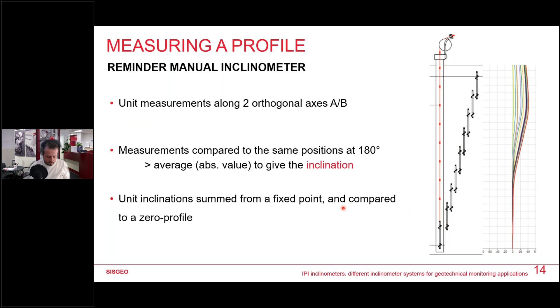So the unit inclinations are summed from a fixed point. You consider that your bottom point, for example, is 0, doesn't move. So it has to be real. If you choose this point as a reference, the reality should be exactly this. This zone will not move. And then you sum your local inclinations step by step in order to get a profile. Then you perform the measurement a second time. So you go on the field, you make exactly the same process, and you retrieve the zero profile from your actual measurement, and then you get deformation compared to the zero measurement. So you get a curve that can be like this on the right. So this is the manual.